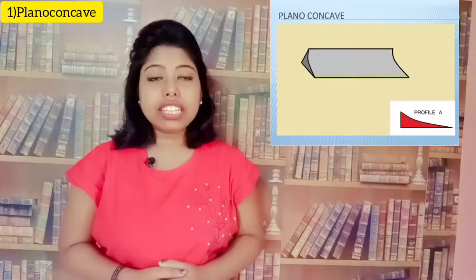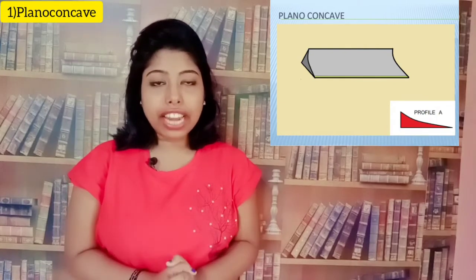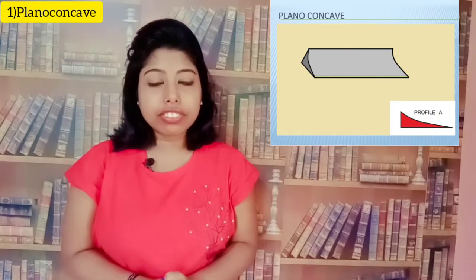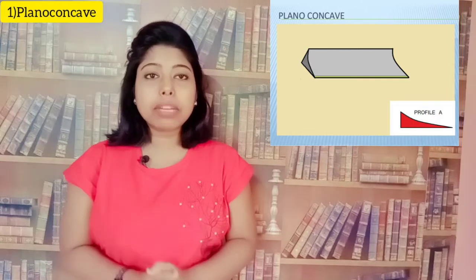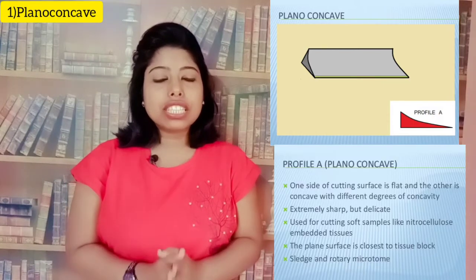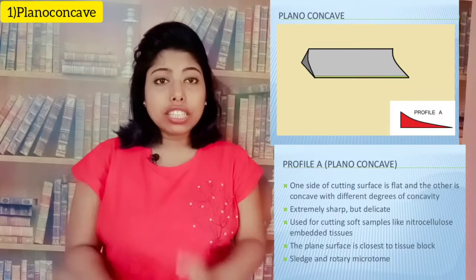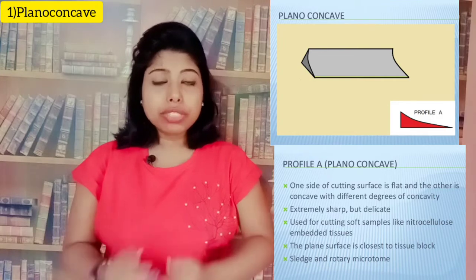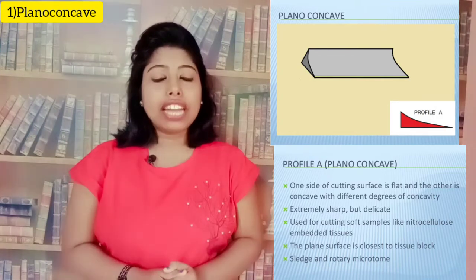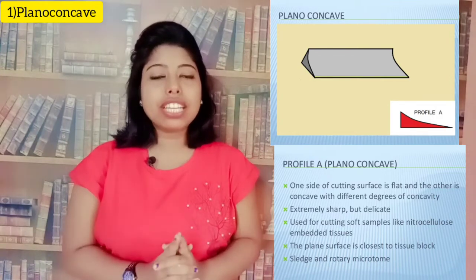The first knife is the plano-concave. One side of the cutting surface is concave and the other is flat — hence the name plano-concave. It is used in the sledge microtome as well as the rotary microtome. It is used for soft samples like nitrocellulose embedding medium and is extremely sharp as well as delicate.